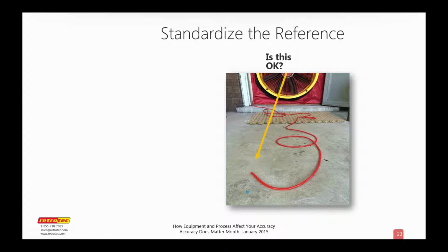Now, it's been my personal experience. In my background as a weatherization person, I've probably seen over 1,000 times where we've done a standard blower test, ASTM residential standard test, where we've had an energy assessor go out to the house, run a blower door test, had a contractor come out afterwards, run a blower door test, same place, same configuration. And then a third time, we've had a quality control inspector come out there and get wildly varying results.